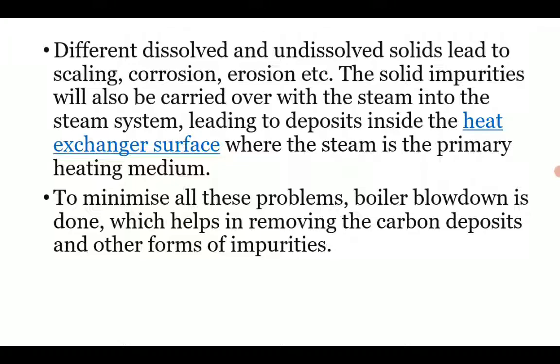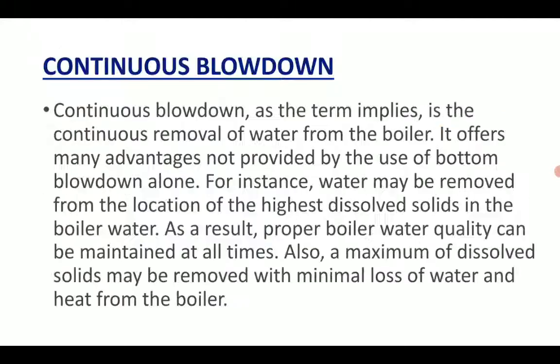Solid impurities will also be carried over with the steam into the steam system, leading to deposits inside the heat exchanger surface, where the steam is the primary heating medium. To minimize all these problems, boiler blowdown is done, which helps in removing the carbon deposits and other forms of impurities. So there are two types of blowdown: one is continuous blowdown and another is intermittent blowdown. First we see about continuous blowdown.